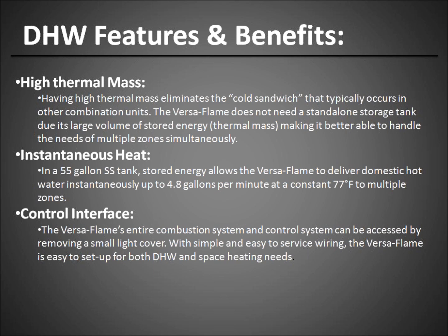Because we have storage and we have a mass of storage heated in a well-insulated vessel, as soon as we start turning on the circulator to flow through the brazed plate heat exchanger, we instantaneously produce large volumes of hot water. So that gives us the ability to do a couple of things. Number one, when you draw very low draws through the brazed plate for domestic hot water, you're not going to short cycle the device because we have a thermal mass we're drawing from. It also gives you a very high peak draw capability to fill tubs and other large demand areas for domestic hot water that normal combination systems that have low mass on both the brazed plate side and also on the heat exchanger have a lot of problems keeping up.